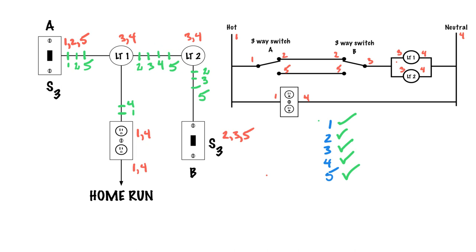You'd find another way to get your circuits laid out, and there are other ways to do that. This is just to show how we can use our schematic to determine how many wires go into something like a piece of pipe — or to determine that the layout you've got won't work because you've got four wires between light 1 and light 2, and there's going to be a better way to connect this circuit up. It's so important to understand how your schematics work: get those drawn up, get them numbered, take those numbers and transfer them to the reality, and then make your hash marks to determine how many wires are in each pipe.